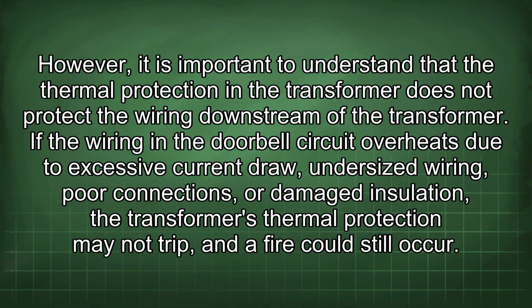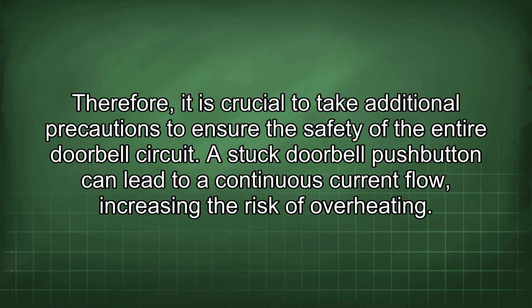However, it is important to understand that the thermal protection in the transformer does not protect the wiring downstream of the transformer. If the wiring in the doorbell circuit overheats due to excessive current draw, undersized wiring, poor connections, or damaged insulation, the transformer's thermal protection may not trip, and a fire could still occur. Therefore, it is crucial to take additional precautions to ensure the safety of the entire doorbell circuit.